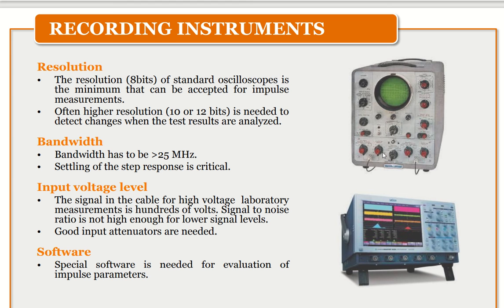And about the bandwidth, okay, this is the specification. The bandwidth has to be more than 25 megahertz. Okay, and then the settling of the step response is critical, and then the input voltage level. The signal in the cable in high voltage laboratory measurement is 100 volt. The signal to noise ratio is not high enough for a low signal, so a good input detector is needed.